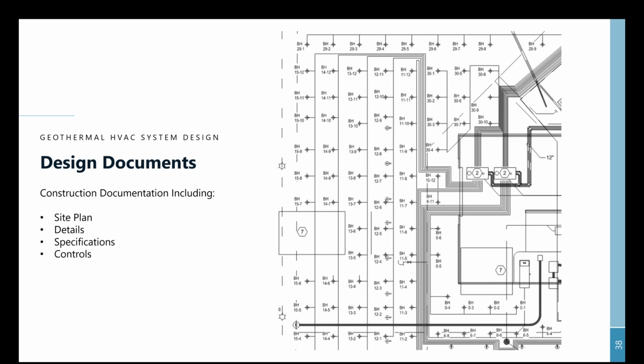There can be up to 10 or 12 boreholes on a single circuit, and each circuit gets its own dedicated number. The site plan is also useful because there are usually other things on site to navigate around, like utilities or parts of the building construction—in this case, large rectangles with keynote 7 marking the footprint for the tower cranes used to build the building. It's important to know which portions of the site are off limits for the geothermal system, so you're not counting on extra boreholes only to find during construction that it's not feasible.